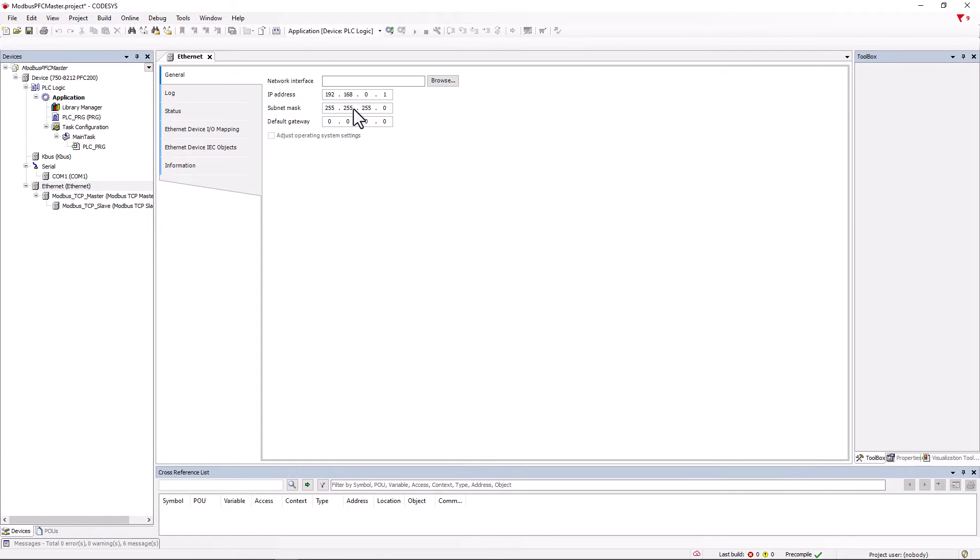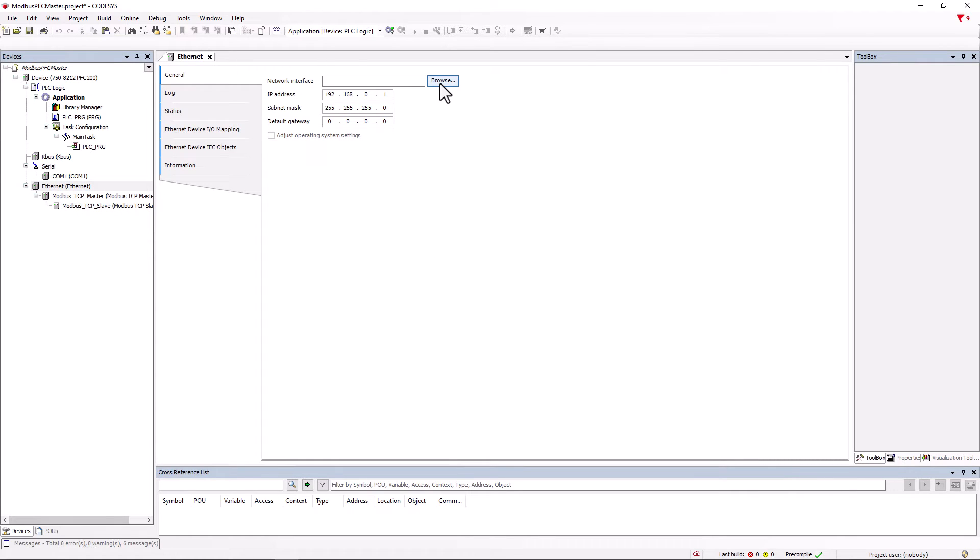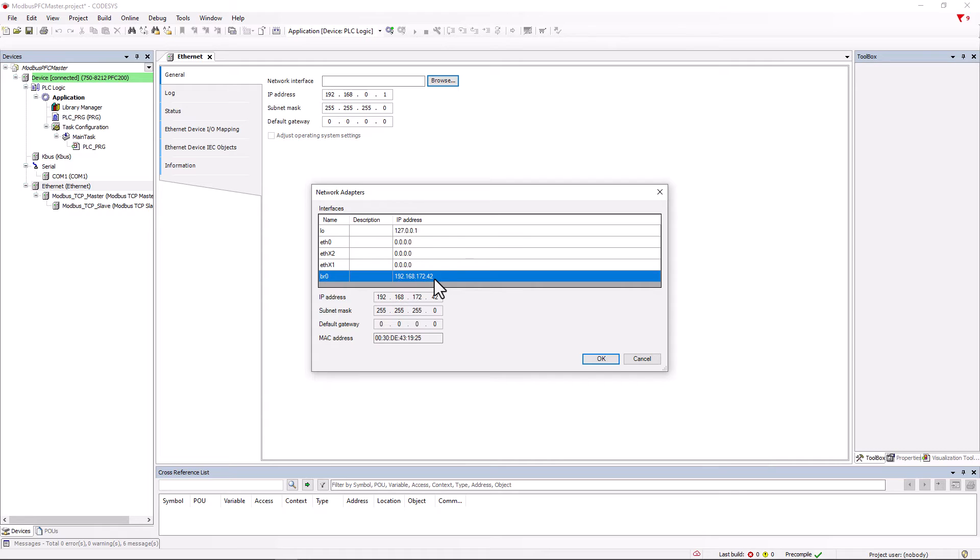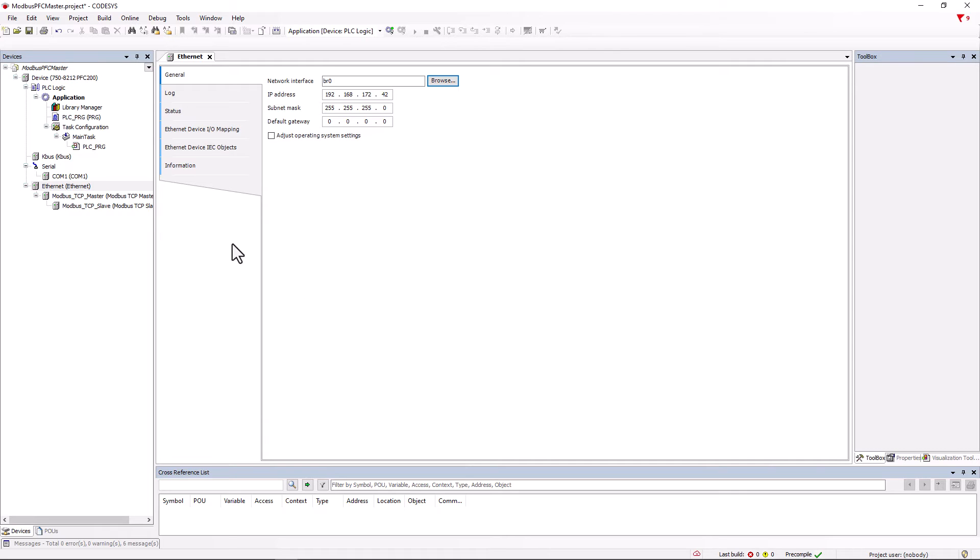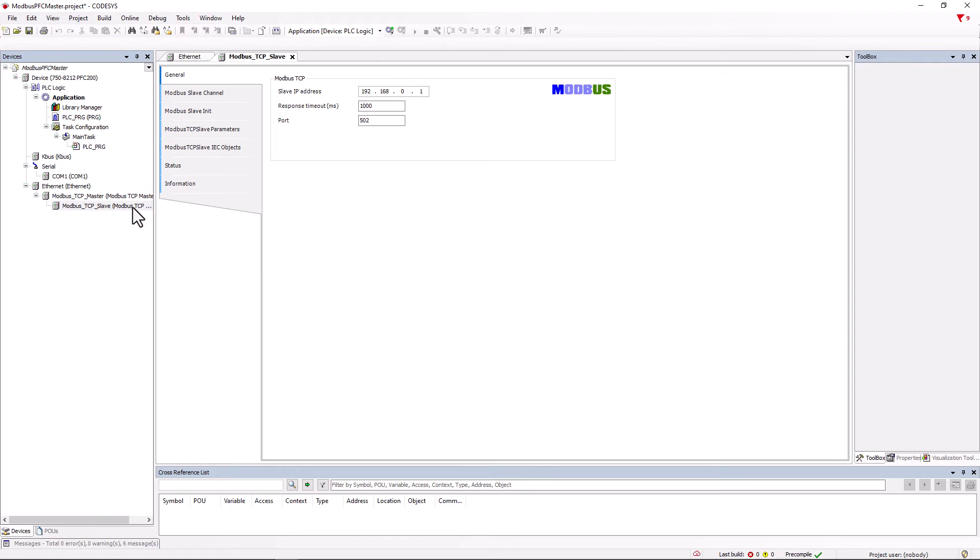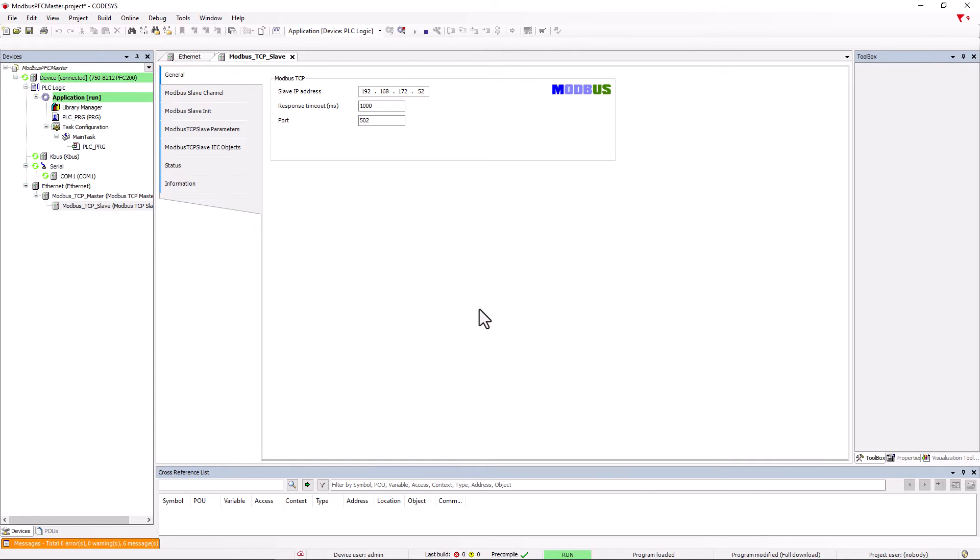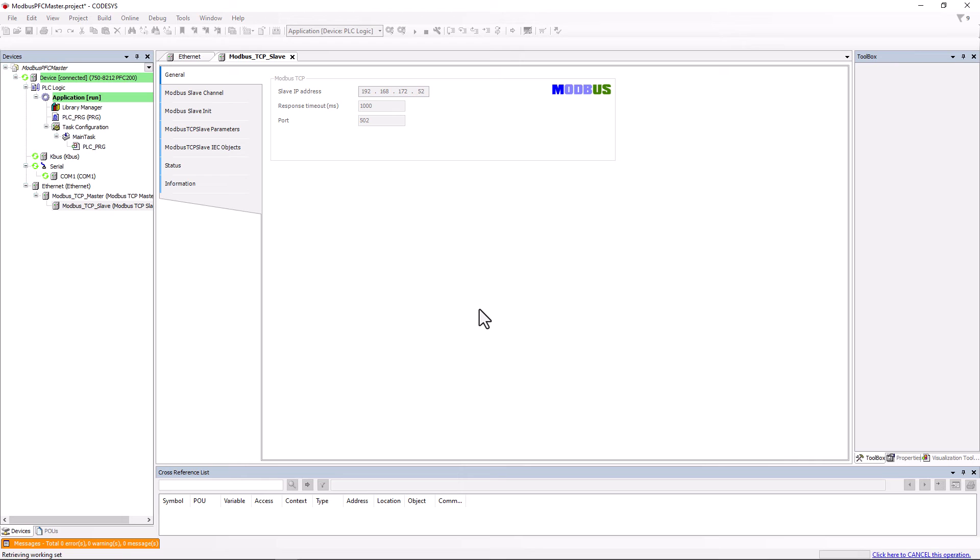So we double click on Ethernet and search for the network interface with the controller IP address using the browse button. Double clicking on Modbus TCP slave opens the slave tab and we enter the slave IP address here, that is, that of our coupler. With this, we have completed the communication settings and we log in as a test.